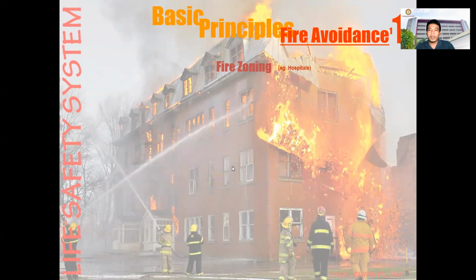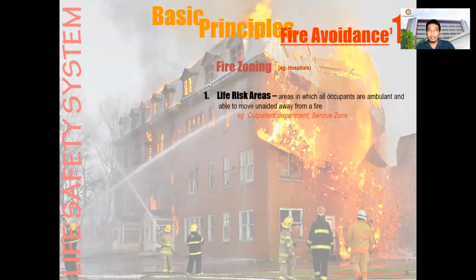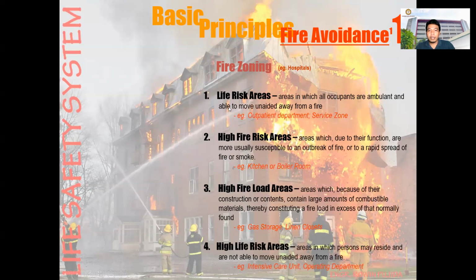So for example, you have in hospital, for fire zoning. So you have life risk area. This is where the area in which all occupants are ambulant and able to move unaided away from a fire. Example, the outpatient department or the service zone. So I am using the hospital as an example here. There are four areas in fire zoning, since only three for the other buildings and four for the hospital.